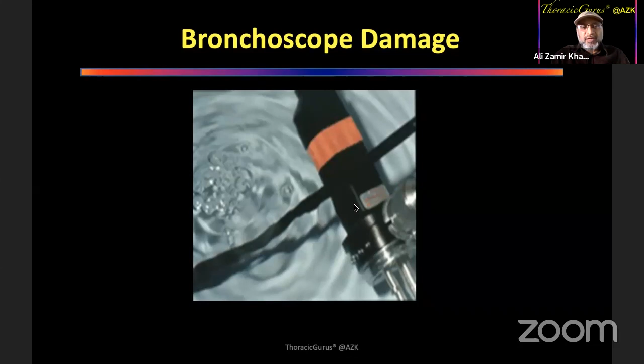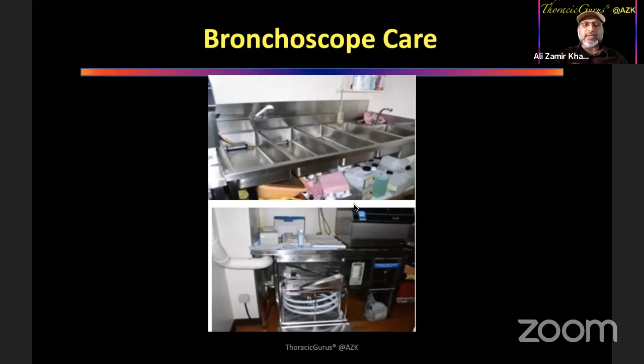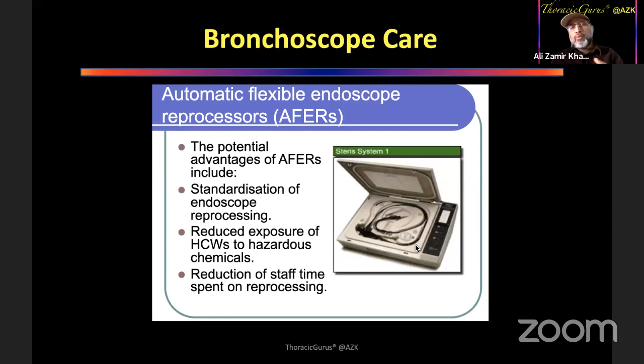Again, whenever we use bronchoscopes, there is always a separate area which is used for cleaning the bronchoscope. There is a separate sterilizer for bronchoscopes. It is a vertical hanging sterilizer where you put the bronchoscopes. And then there is another device available, which is called an automatic flexible endoscope reprocessor. So you put it all properly into these channels so that they are not bent too much. And then you close it, and it gets reprocessed with all the various chemicals, and then the bronchoscope comes out on the other side sterile.